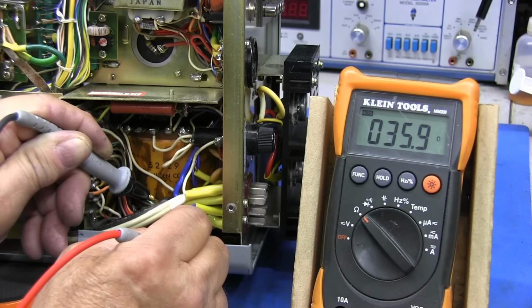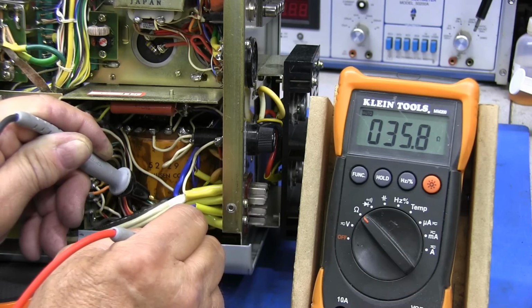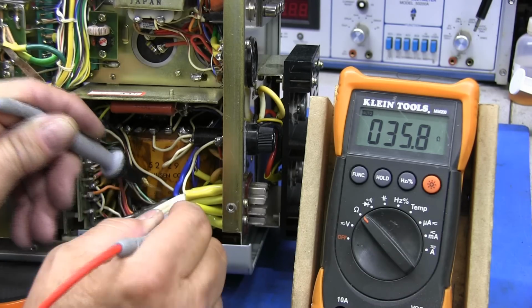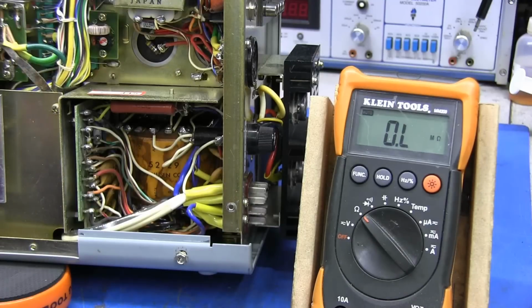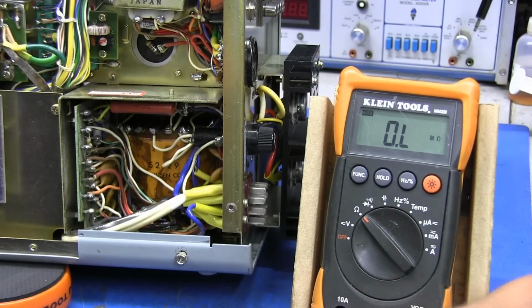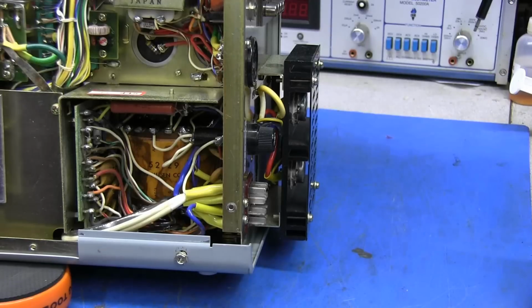And we got 35.9 ohms. Well, that's good. That's telling me that winding in the transformer is good.